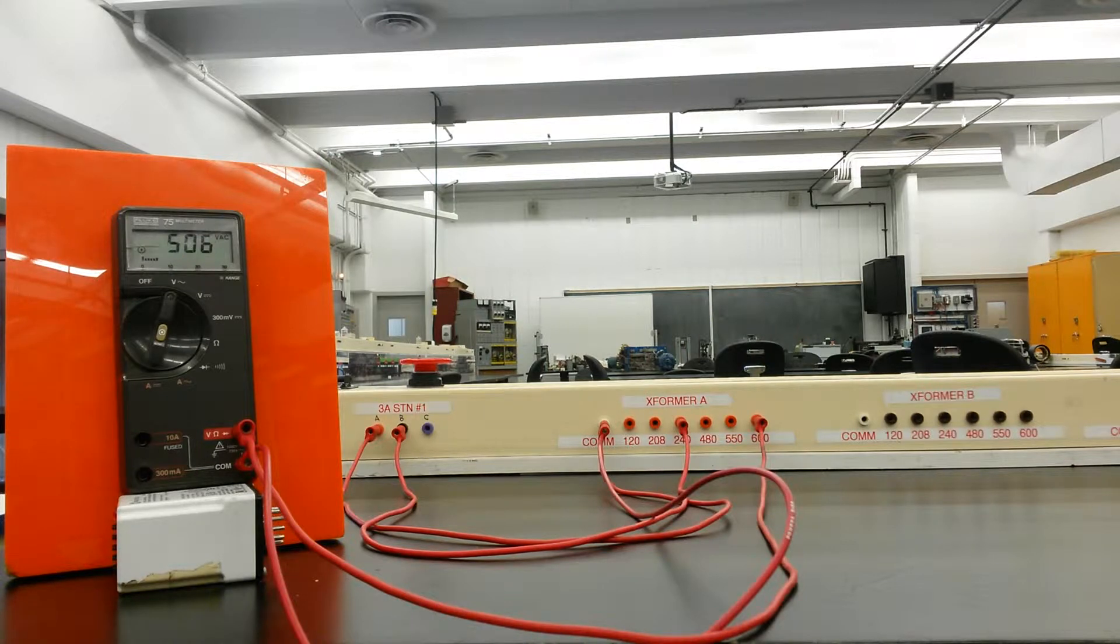Okay, so now instead of seeing the 600 volts, I'm down to 500. Right, the ratio has now changed on all of the windings of the entire transformer.